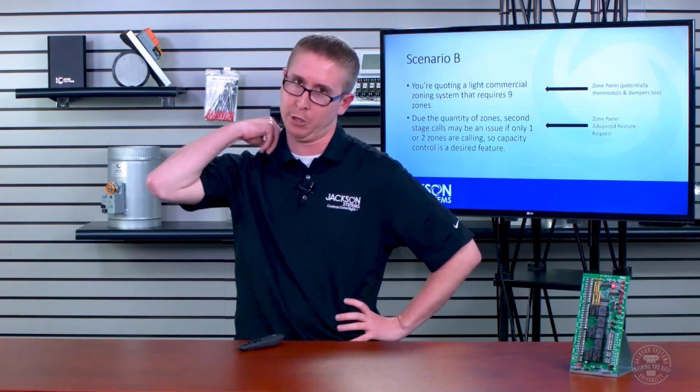We ship it at 0.35 inches of water column, I believe, but that is a huge benefit to that system, just how easy it is to adjust at what static pressure you want that to start opening the non-calling zones.